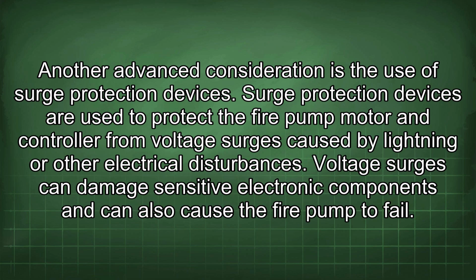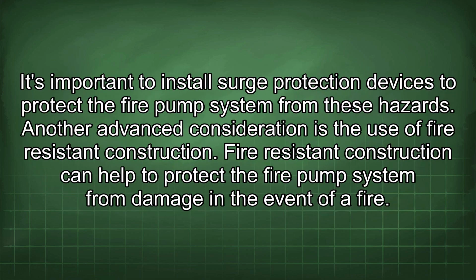Surge protection devices are used to protect the fire pump motor and controller from voltage surges caused by lightning or other electrical disturbances. Voltage surges can damage sensitive electronic components and can also cause the fire pump to fail. It's important to install surge protection devices to protect the fire pump system from these hazards.